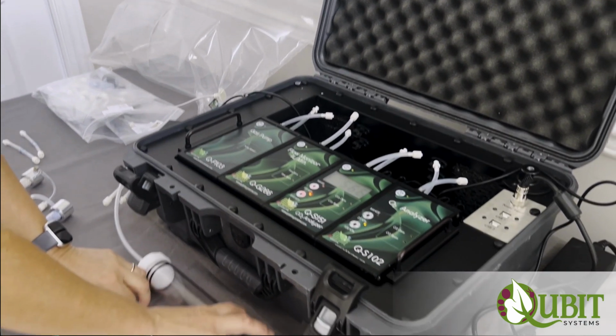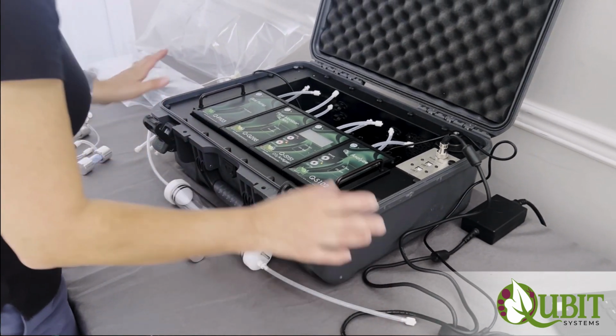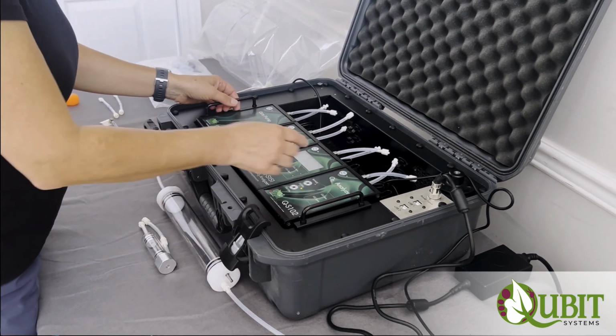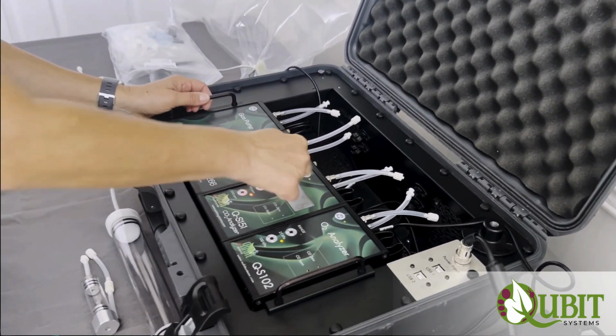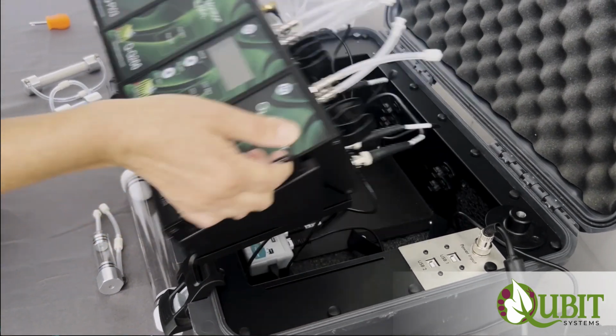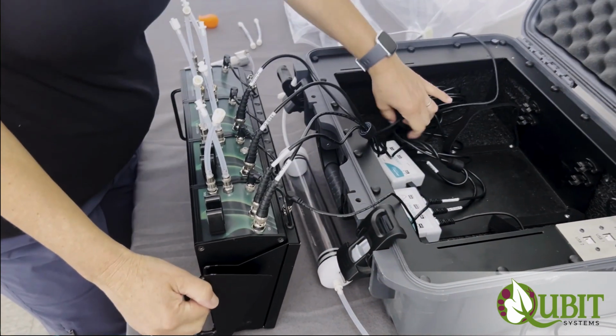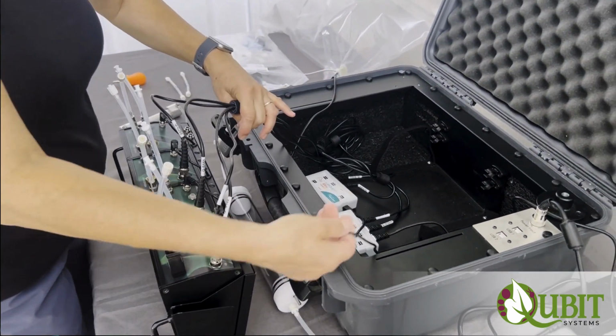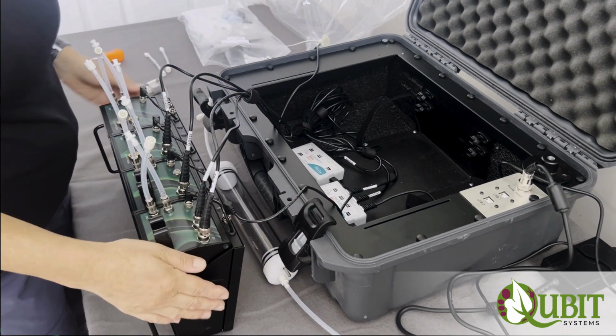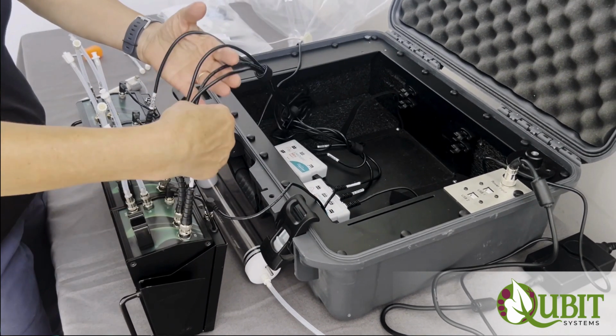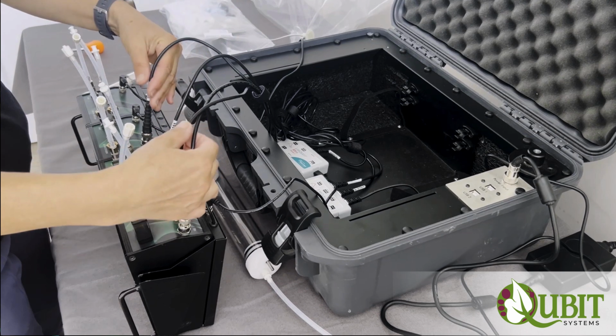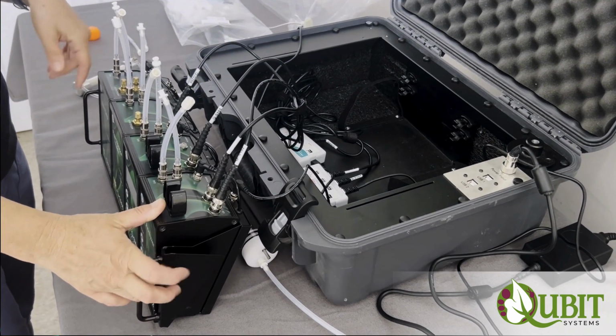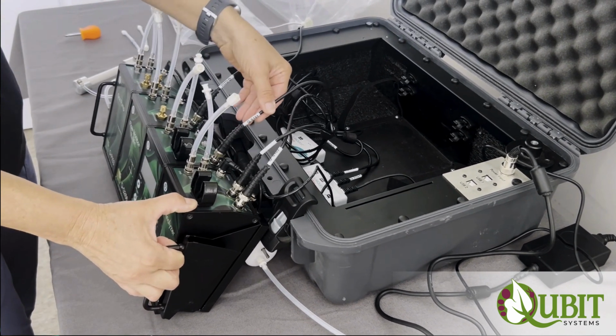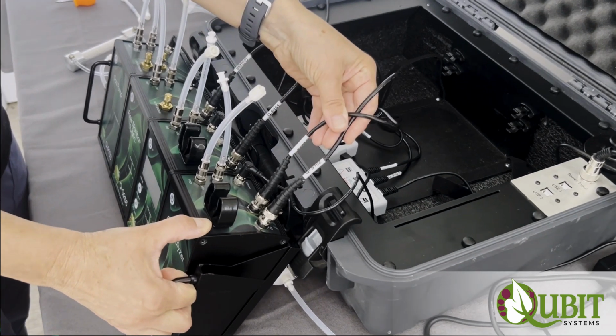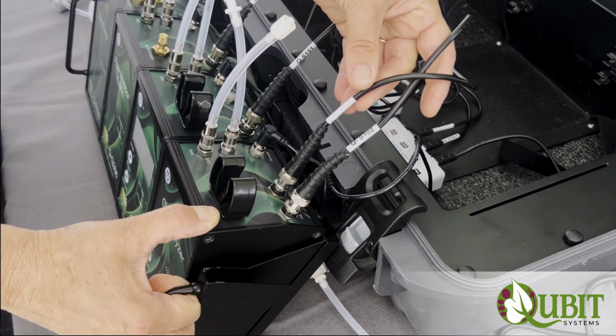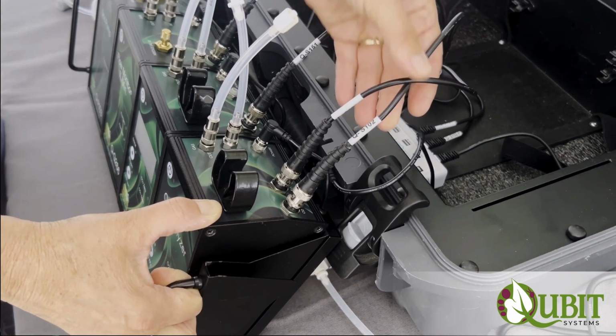The first thing that you need to do is to check that everything is connected. I have everything turned on at the moment. I'll turn these off. But the first thing you want to do is make sure that everything is connected and powered. The power is coming from the Q Box to the main analyzer tray. Then we have data cables which carry the signals from the various sensors, from the flow monitor, CO2 analyzer, and there are two data cables from the oxygen analyzer. One is for oxygen, one is for pressure.